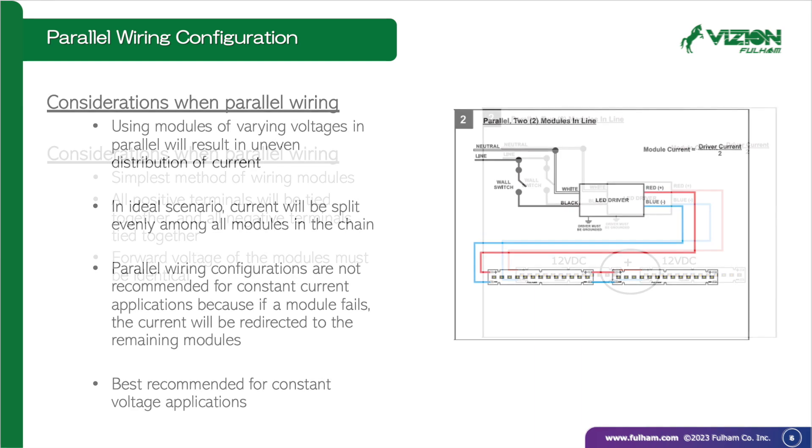With ideal module voltages, the output current of the LED driver will be split evenly by the number of modules in the chain. Please note that these wiring configurations are not recommended for constant current module applications, because failure of one module will cause all the current to redirect to the remaining modules. These are best recommended for constant voltage applications.